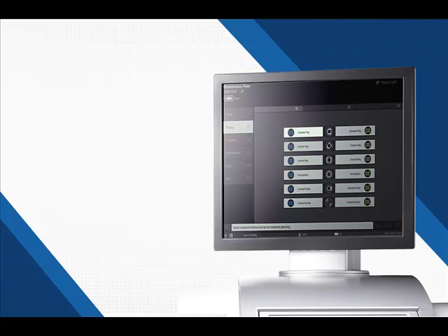And then the benefits for the surgeon: a small universal patient interface makes the procedure quicker. They have more confidence in what the laser is doing. The low pressure means they can treat patients with glaucoma, so they're not losing business. They're not having to restrict what they can do within their surgical center. The docking process is simplified and very intuitive because the eye slips into the contact lens. And we don't have to put a belt on the patient's head, so for those with claustrophobia, it's a much more comfortable process.